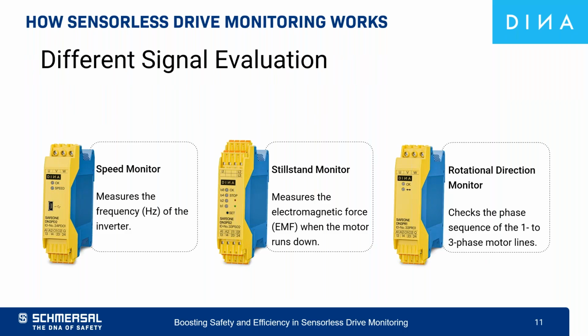The speed monitoring module measures the frequency output by the frequency inverter to the motor. It calculates the speed of the motor. Since the inverter's frequency is directly proportional to the motor's synchronous speed, the device can determine the current motor speed indirectly and without an external sensor. This module can be used for both 3-phase and 1-phase applications.